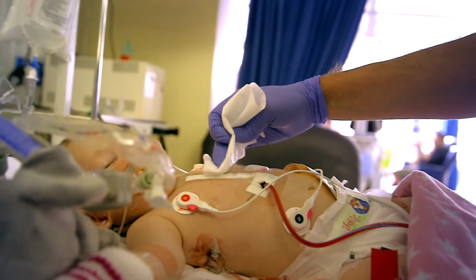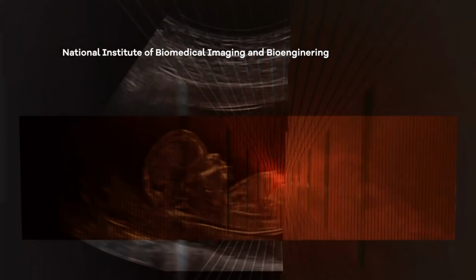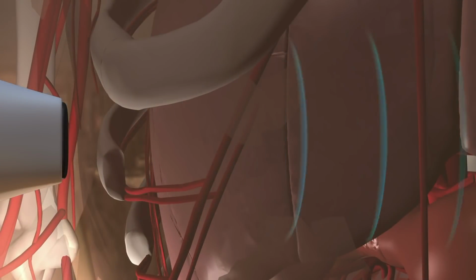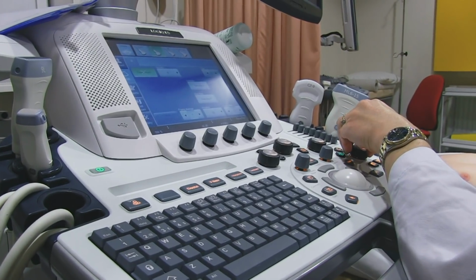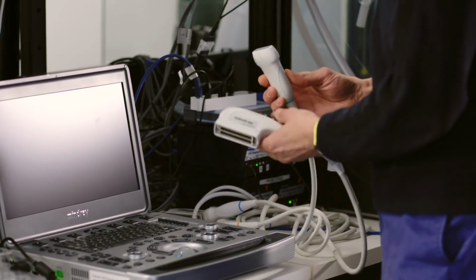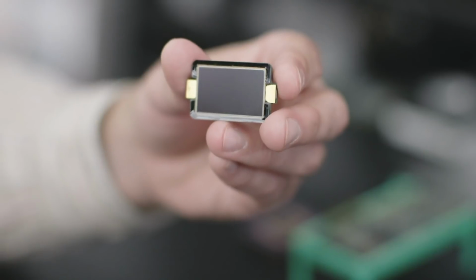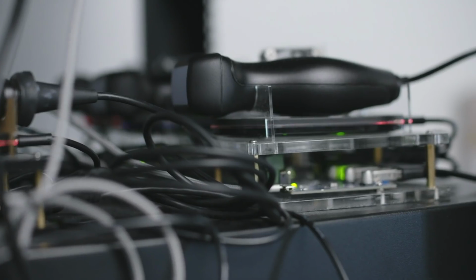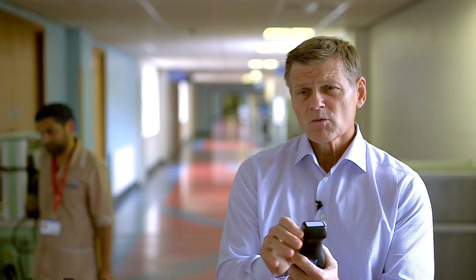Good girl, well done. Traditional ultrasound machines use piezoelectric crystals, individual crystals cut into different shapes and sizes as different frequencies are used to image different parts of the body. But this also means that different probes are needed. The Butterfly uses ultrasound on a computer chip and needs only one probe for different body parts. We're the world's first ultrasound on a chip, a single probe, whole body imaging system. Instead of the typical 124 imaging elements that are in a PZT probe, there are almost 9,000 elements in this. And so we can recreate all the different types of probes with just one.